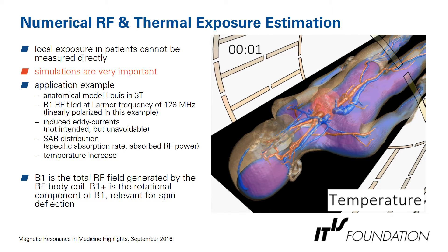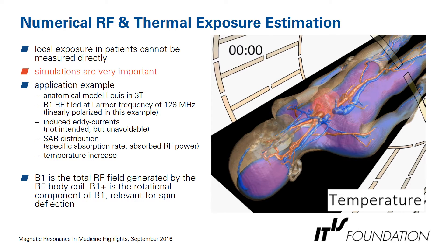Where we have a high concentration of these currents, we also have a high local deposition of RF energy. That's what you can see in the SAR distribution slides. We have a hotspot in Louis near the neck region. Subsequently, we can do a thermal simulation with the SAR distribution as input, where you see that with time — 5, 10, 15 minutes — we heat up the tissues, especially at these hotspots.